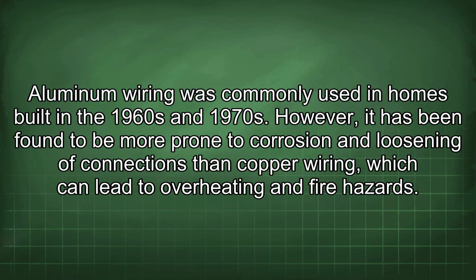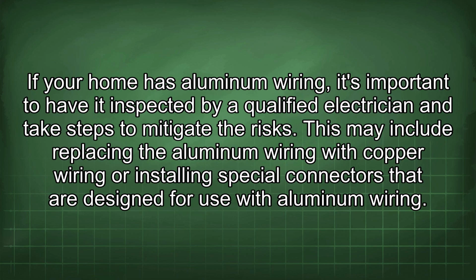Aluminum wiring was commonly used in homes built in the 1960s and 1970s. However, it has been found to be more prone to corrosion and loosening of connections than copper wiring, which can lead to overheating and fire hazards. If your home has aluminum wiring, it's important to have it inspected by a qualified electrician and take steps to mitigate the risks. This may include replacing the aluminum wiring with copper wiring or installing special connectors that are designed for use with aluminum wiring.